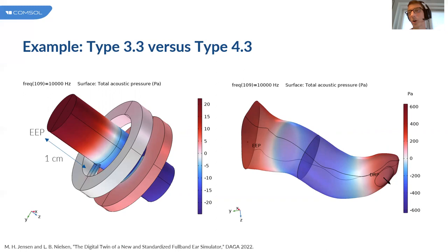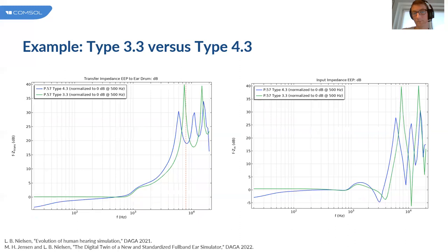It has a more anatomically correct geometry also. The colors in this plot are the pressure response at 10 kilohertz. Comparing the Type 3.3 and 4.3 simulators, Type 4.3 blue curve, Type 3.3 green curve. On the left we look at the transfer impedance and at the right we look at the input impedance of the system. At the higher frequencies above six, seven, eight kilohertz, there's a big discrepancy between the two systems. This is the other reason for developing the new full band Type 4.3 ear simulator to actually get a more correct high frequency response of the ear simulator.